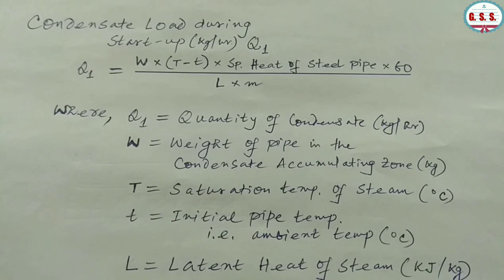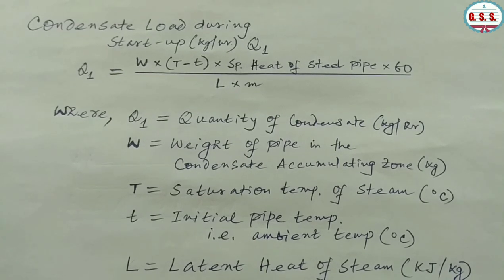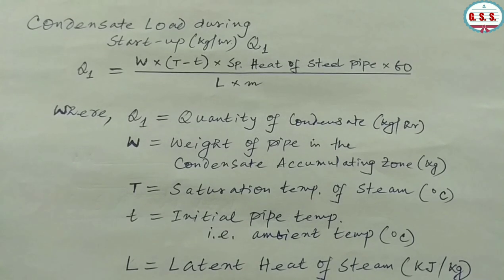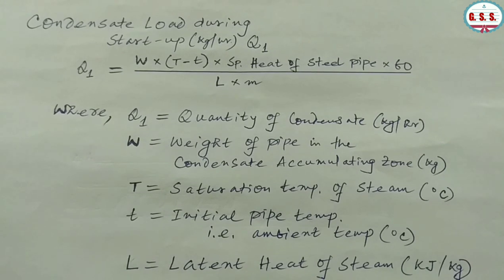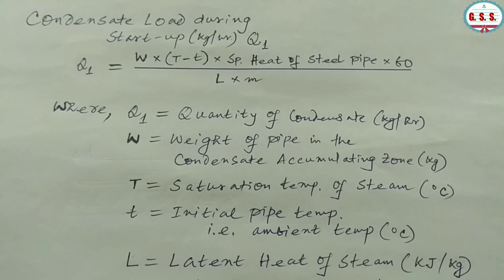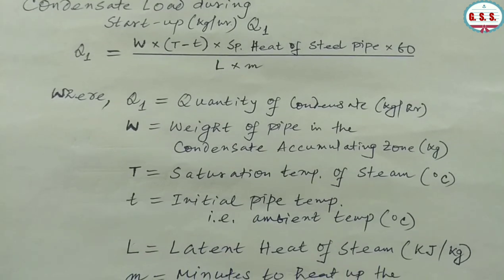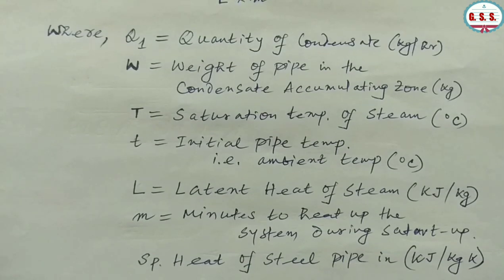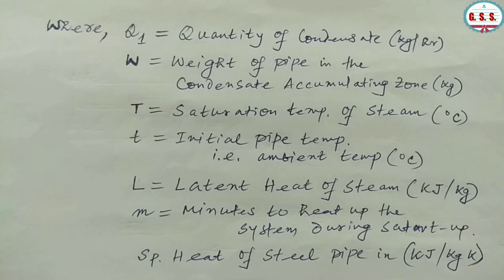Condensate load during startup means the amount of condensate that forms to warm up the pipeline during initial startup. Q1 = (W × (T − t) × specific heat of steel pipe × 60) / (L × M), where Q1 is quantity of condensate in kg/hr, W is weight of pipe in the condensate accumulating zone in kg, T is saturation temperature of steam in °C, t is initial pipe (ambient) temperature in °C, L is latent heat of steam in kJ/kg, M is warm-up time in minutes, and specific heat of steel pipe is in kJ/(kg·K).